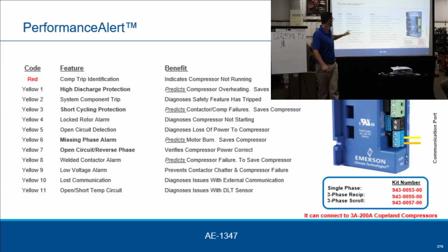And these electronics, look what it protects against. High discharge, short cycling, missing phase, open or reverse phase. Then you can take a computer and log into it and see how many hours it ran, how many times it tripped off, how many times it locked out. And also you can connect to these two systems, like our E2 system. You can network to it, so you can remotely dial in to see how that compressor is running.